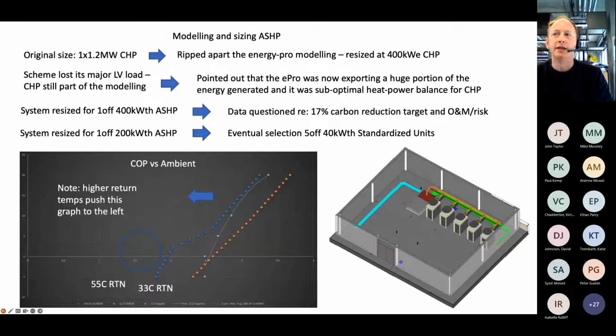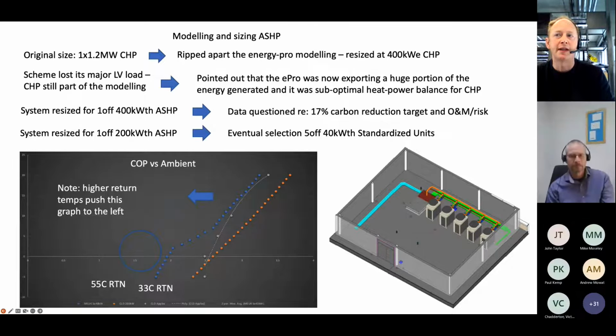We pointed out that you only needed to hit a certain percentage of carbon reduction target for the scheme, and that to do this, we'd likely be running the air source mostly at night because of the low energy use pricing, and also only at times of the year when the ambient temperatures were over 5 degrees C, and we'd be using the boilers the rest of the time. And that changed their modeling, that changed their thinking. And also, you can see this grey line.